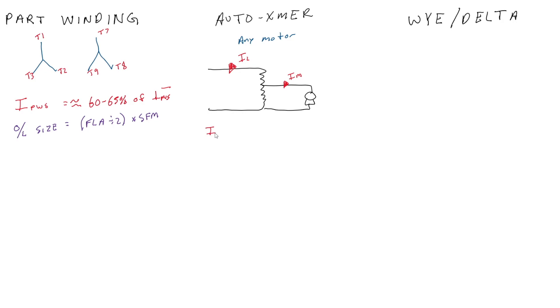The motor current at start using an auto transformer starter is equivalent to the full voltage starting current times the tap setting. The line current at start — where you would place your overcurrent devices, breakers, and disconnects — is your full voltage starting current times the tap squared. We see a double reduction there because the transformer maintains its KVA in and KVA out.